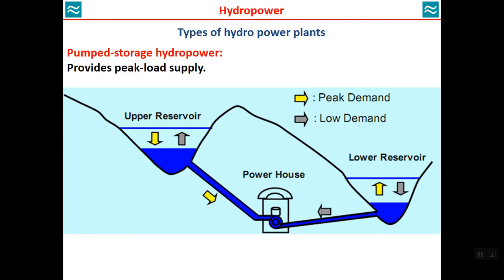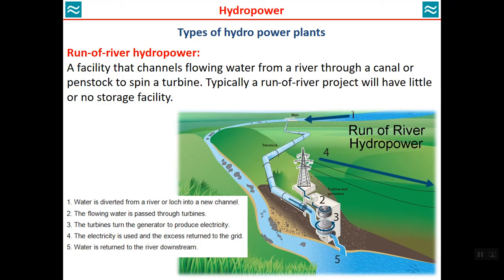A very interesting type is pumped storage hydropower. It has two reservoirs — upper and lower. When demand on the power grid is low, water is pumped from the lower reservoir to the upper reservoir for storage. During peak demand times, such as summer afternoons or evenings, water is directed from the upper reservoir back to the lower one through turbines to generate power. This is a very interesting type of hydropower plant.